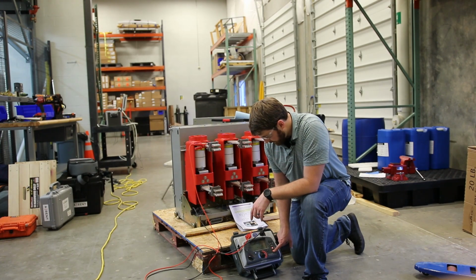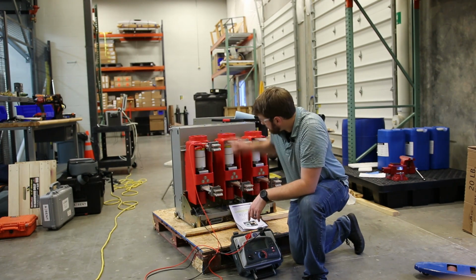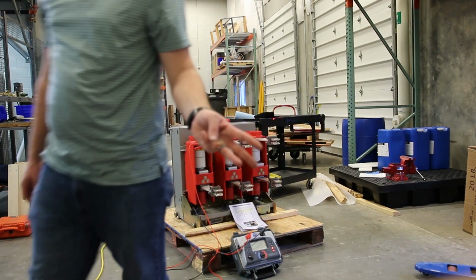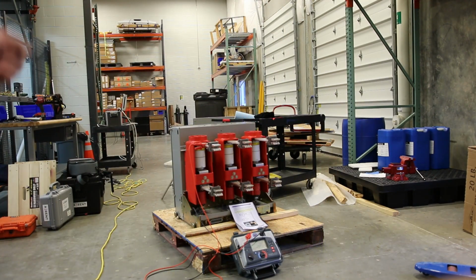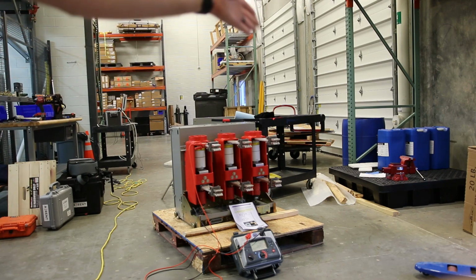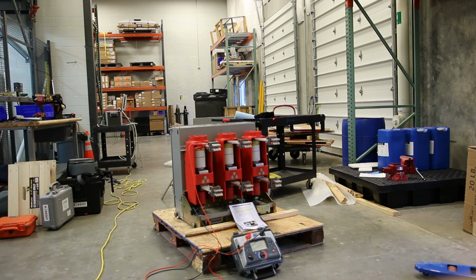So just like that, we've got our megger set to 2500 volts. We're gonna do that 3 times, A phase ground, B phase ground, C phase ground. And then we're gonna do A to B, A to C, B to C, and then we'll open it and go across the vacuum bottles. And I'm gonna speed this part up because it's boring.